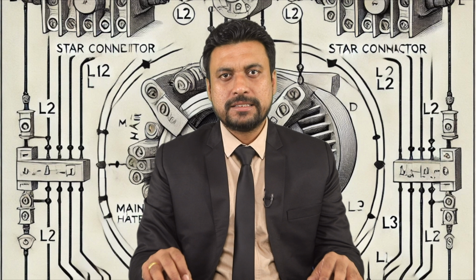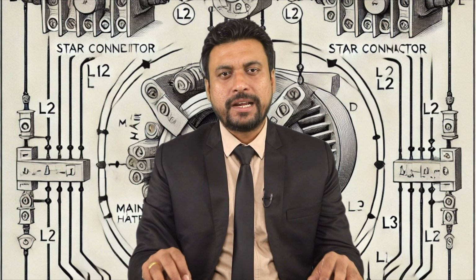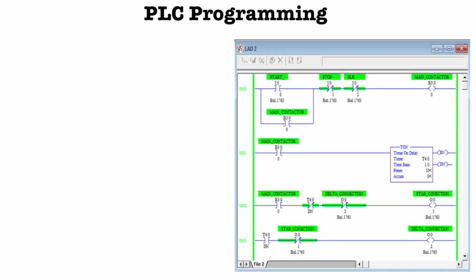The star delta starter system typically consists of three main contactors, as you can see in the diagram. One for the star connection, one for the delta connection, and one for the main power supply. A timer is used to control the duration of the star phase before switching to delta. Additionally, an overload relay is incorporated to protect the motor from overcurrent situations by disconnecting the power if the current exceeds a safe limit. Now, let's see the PLC program or ladder logic for the star delta starter.